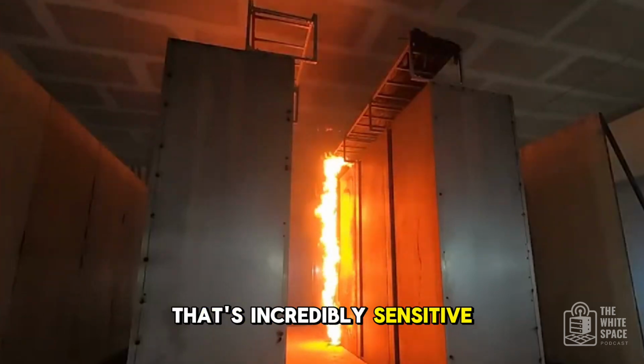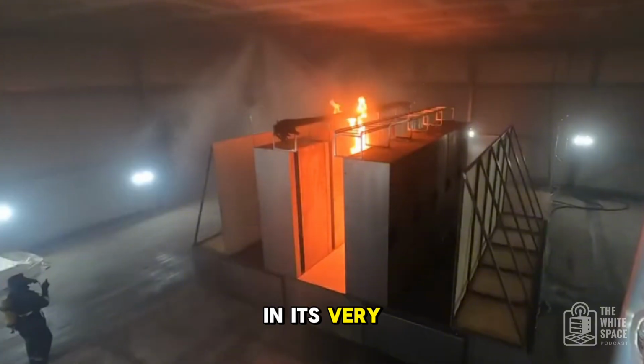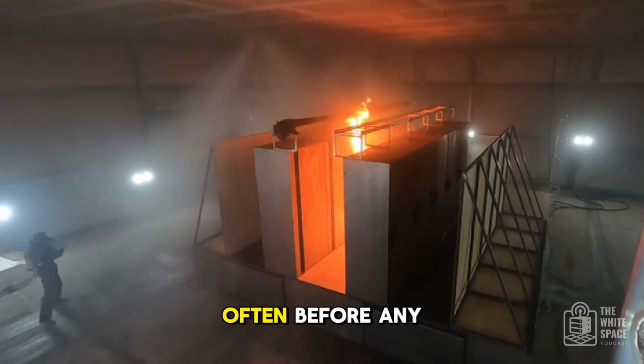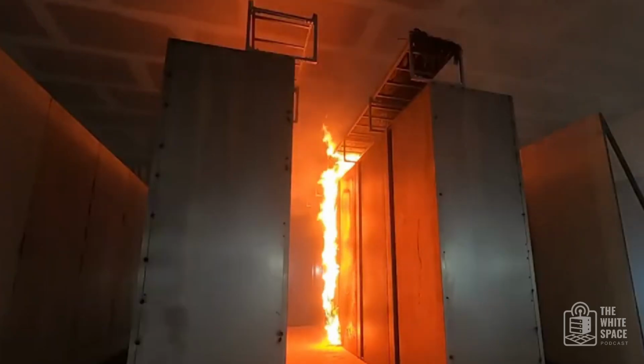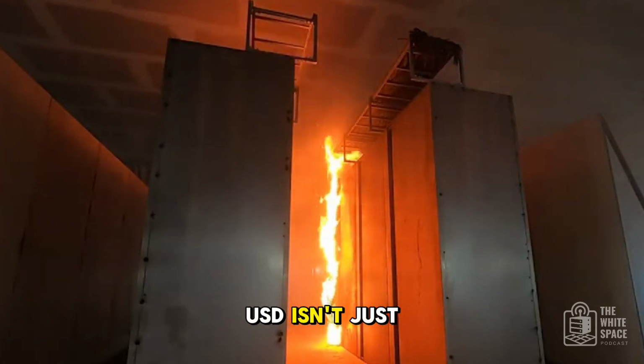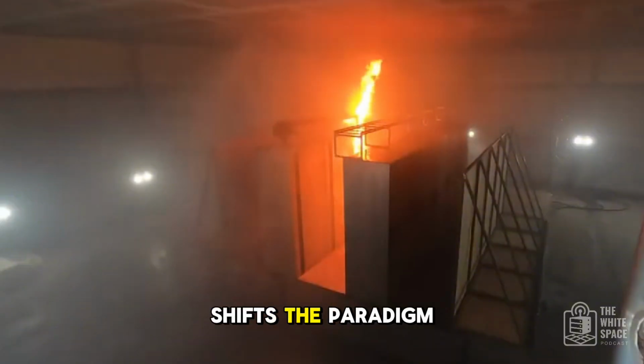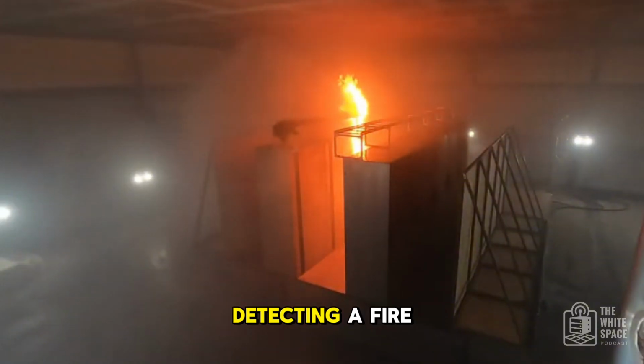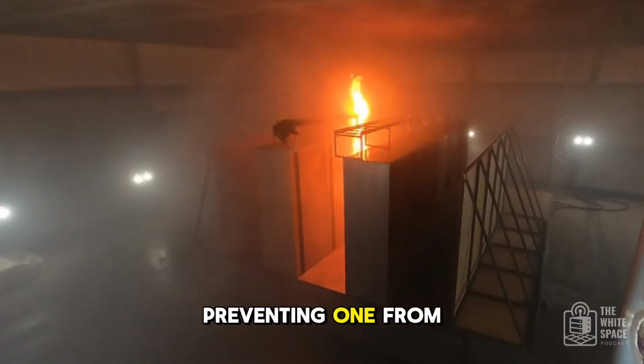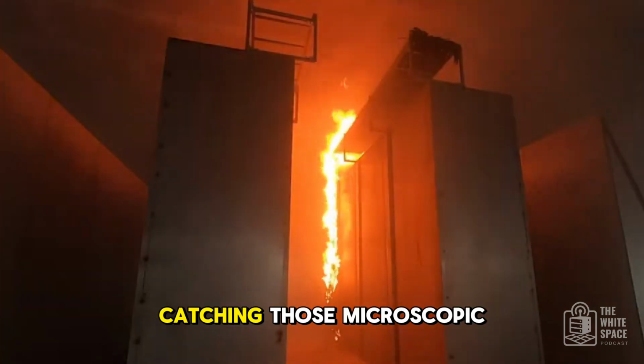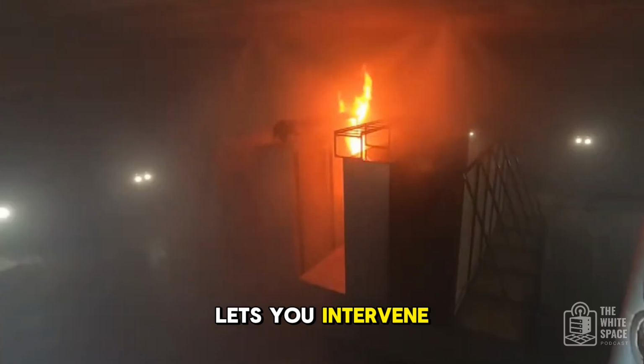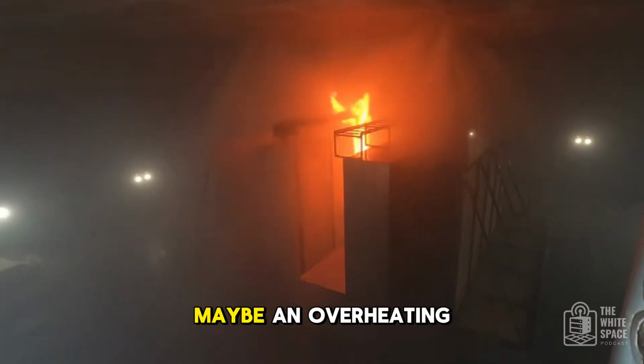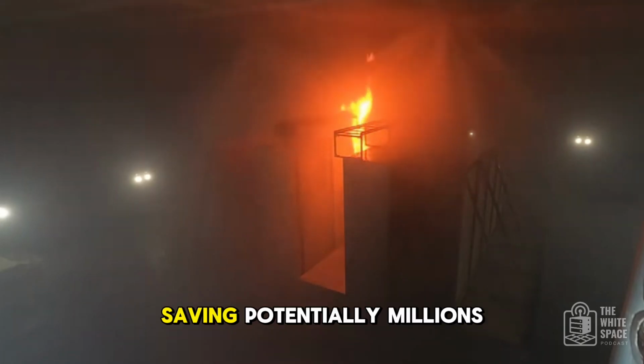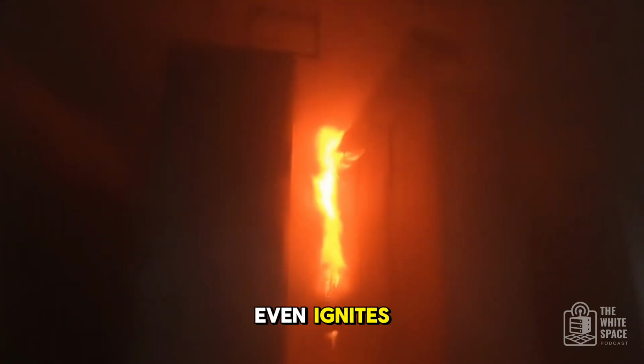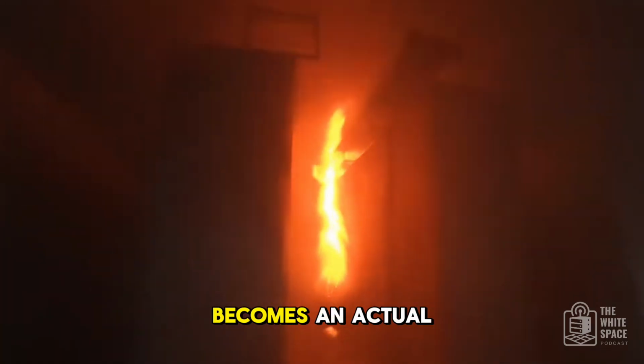That's incredibly sensitive. It means detecting a fire in its very, very earliest stage, often before any visible smoke or heat. The real power of VESDA isn't just sensitivity, it's that it shifts the paradigm. It's less about detecting a fire and more about preventing one from truly taking hold. Catching those microscopic signs lets you intervene when it's just a potential issue, maybe an overheating component, saving potentially millions before a flame even ignites. So you can investigate before it becomes an actual fire.